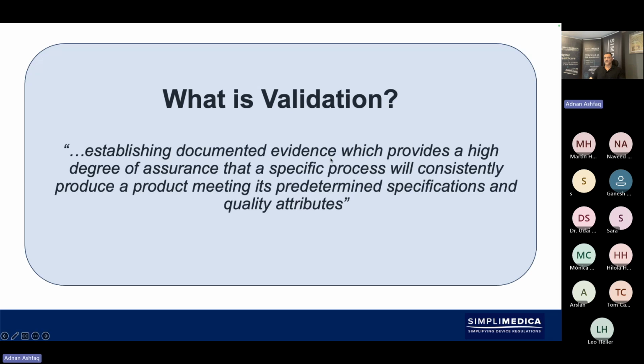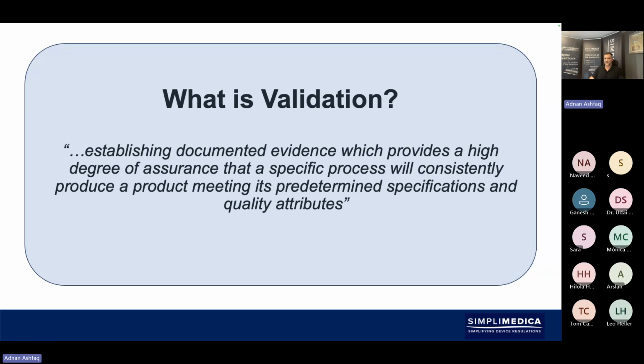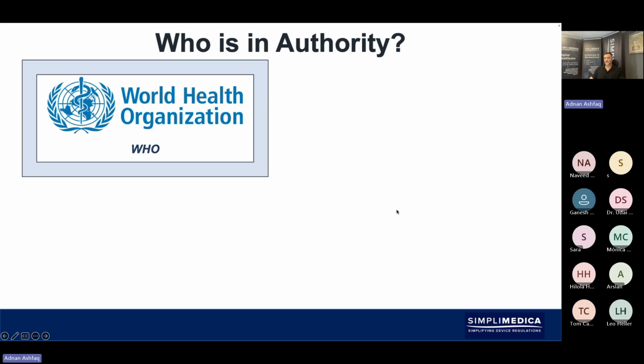So the question, what is validation? We looked at the definitions earlier. We've got the FDA, there's also a WHO definition, and there are other definitions also. ISO 13485 we've looked at, and we're focusing a bit more on that 7.5.6, which again states, in inverted commas, establishing documented evidence which provides a high degree of assurance that a specific process will consistently produce a product meeting its predetermined specifications and quality attributes. I mean, every part of that sentence is so important, whether it's the high degree of assurance, whether it's a specific process that will consistently produce the product, and the predetermined specifications, because you cannot validate something without predetermined specifications and acceptance criteria. So we must know what the acceptance criteria is that we're looking for. Otherwise, we don't know what a pass-fail criteria may be.